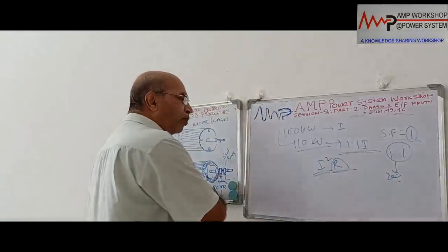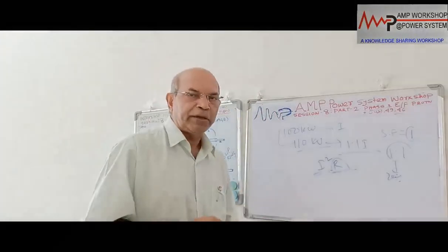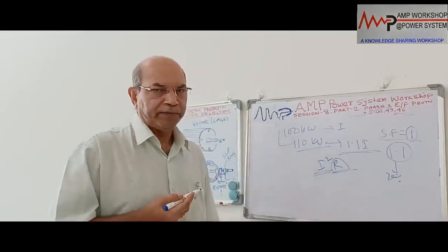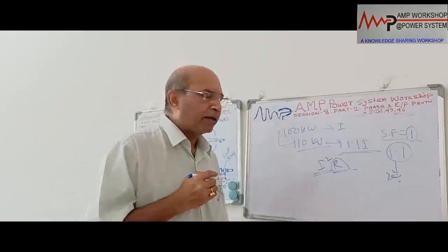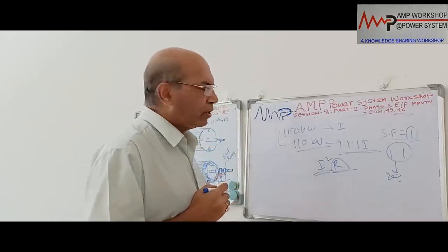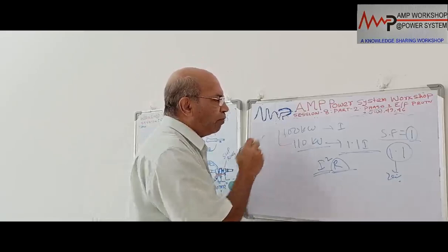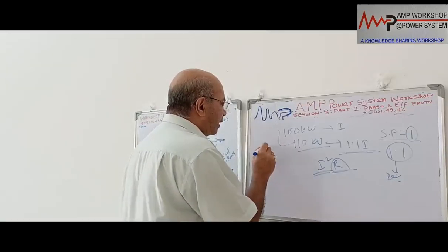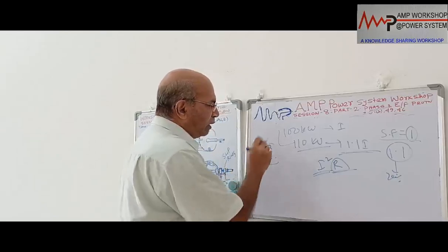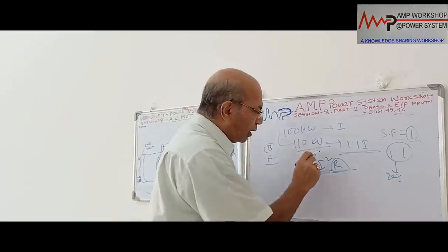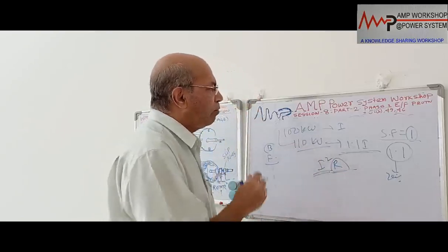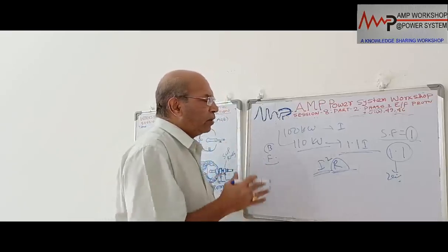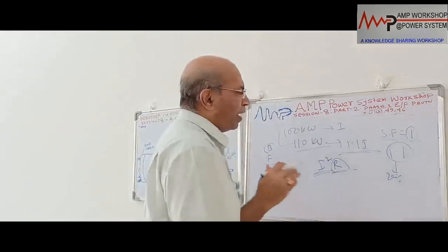But if we go more than 10%, then the motor insulation will get damaged. And we already discussed that for every 6 degree rise of temperature, insulation life becomes half. We already discussed that a long time back during a previous general discussion. So insulation is an important point for the motor, because normally we give a motor F type insulation, with temperature rise limited to class B. That is the insulation class of the motor. So if we allow overloading, then the motor insulation will deteriorate and ultimately the life of the motor will get less. So that's why we have to provide overload protection in the motor.